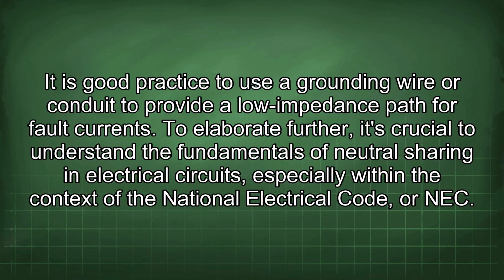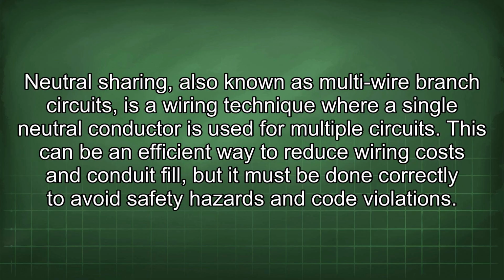To elaborate further, it's crucial to understand the fundamentals of neutral sharing in electrical circuits, especially within the context of the National Electrical Code, or NEC. Neutral sharing, also known as multi-wire branch circuits, is a wiring technique where a single neutral conductor is used for multiple circuits. This can be an efficient way to reduce wiring costs and conduit fill, but it must be done correctly to avoid safety hazards and code violations.